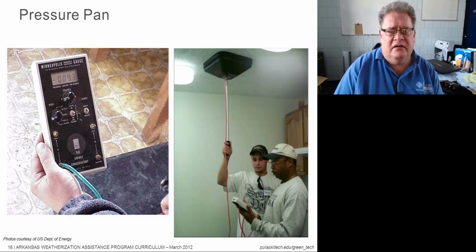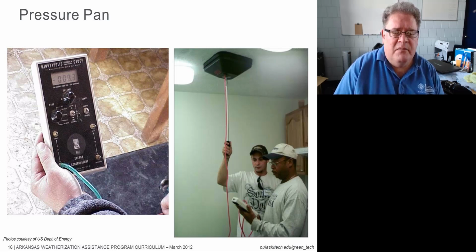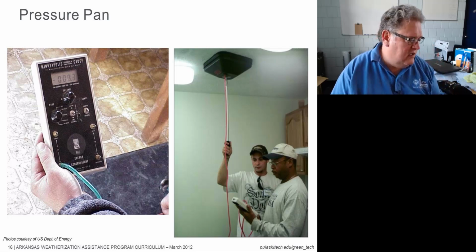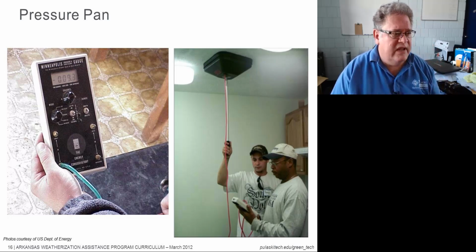These are pretty good instruments. There's nothing wrong with them. As a matter of fact, really the only difference between these and a DG700, as far as the equipment that's in them, as far as I know, the sensors are fairly much the same. It is just the switches and the controls and then the display and the software to run all of that that's been changed out. But as far as what's actually seeing and generating the signal for the little computer in there to use, it's the same. Somebody correct me if I'm wrong, but my point is this is still a perfectly good manometer. If you're concerned about the calibration, do a field check on it. If not, send it in to the manufacturer and see what they say.